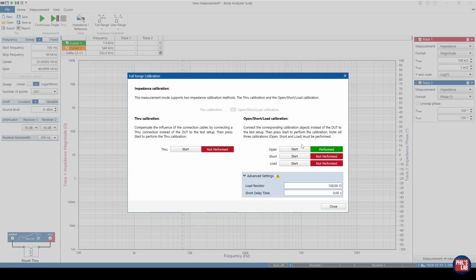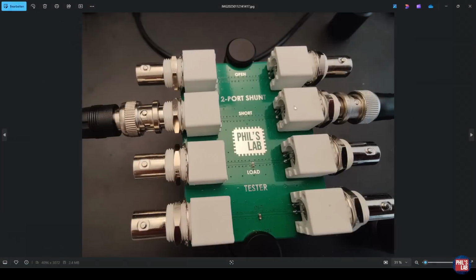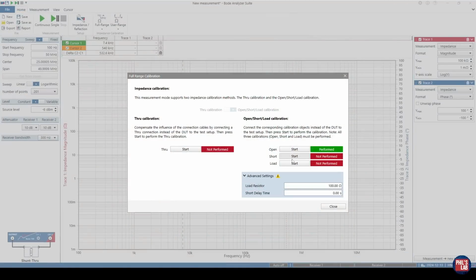Now we've done the open calibration, let's move over to the short. So having moved over the BNC cables, exactly the same measurement setup, except now I'm hooking up to this short interface, which is just a short to ground right at the center, appropriately sized for 0603 type components. With that in place, click on short and that'll run through. Again, check out the receiver 1, receiver 2 signal strength. And for a short, that's of course going to be much lower because we're shunting essentially the energy pretty much directly to ground to the 50 ohms.